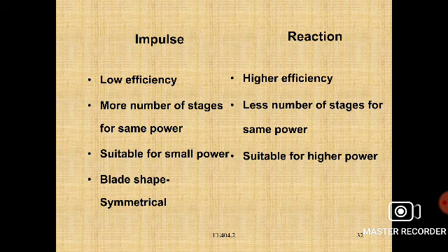Right, these are the classification and differences between the impulse turbine and reaction turbine. The impulse turbine has low efficiency and the reaction turbine has higher thermal efficiency. More stages are placed inside an impulse turbine, and fewer stages for the same power in a reaction turbine. Impulse is suitable for small power, reaction for higher power. The blades are symmetrically shaped in impulse and aerofoil in reaction.